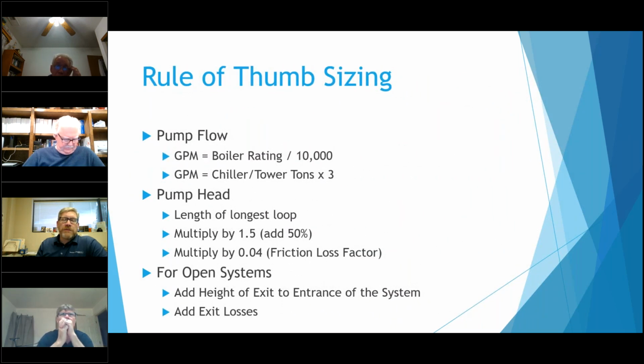So, just a rule of thumb sizing. A lot of times you get out there and you just need to have something to go off of. Basically, it's the boiler rating divided by 10,000, or if you're doing cooling, chiller or cooling tower tonnage, multiply that by 3 to get your GPM.